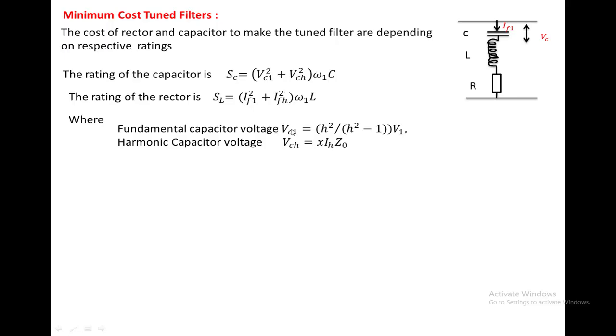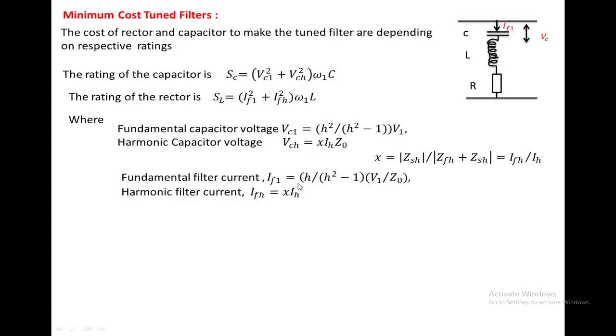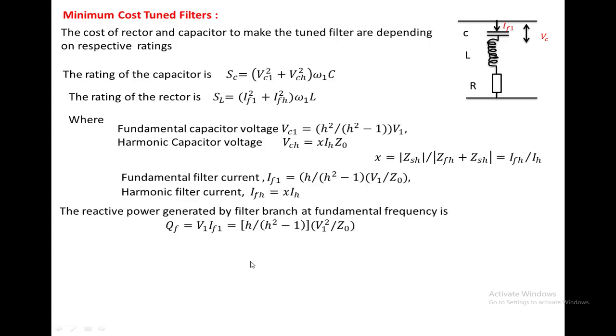The fundamental capacitor voltage VC1 equals H²/(H²−1) · V1, where H is the harmonic order. The harmonic capacitor voltage VCH equals X·IH·Z0, where IH is the harmonic current and X equals ZSH/(ZFH + ZSH), which also equals IFH/IH. The fundamental filter current IF1 equals H/(H²−1) · V/Z0, and the harmonic filter current IFH equals X·IH. The reactive power generated by the filter branch at fundamental frequency is QF = V1·IF1 = H/(H²−1) · V²/Z0.